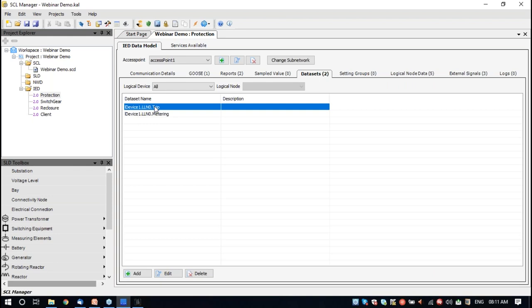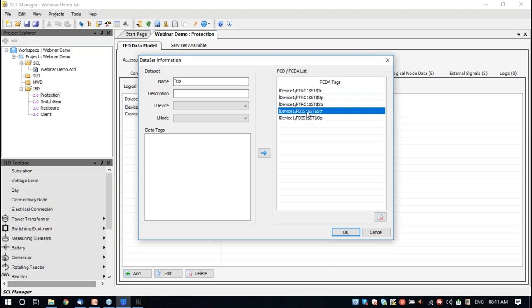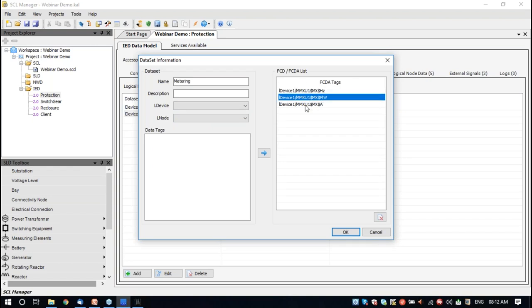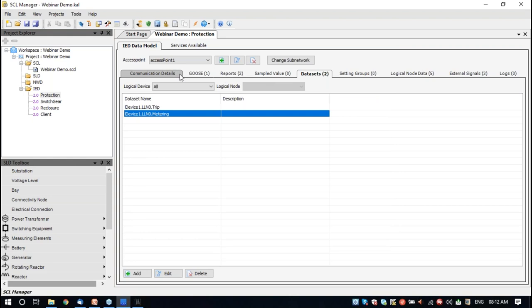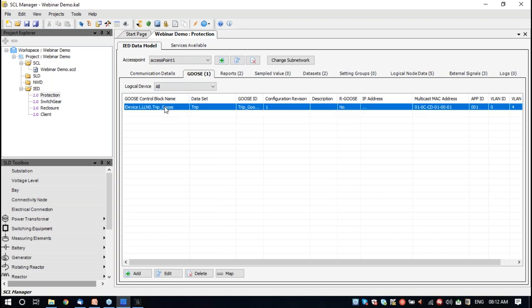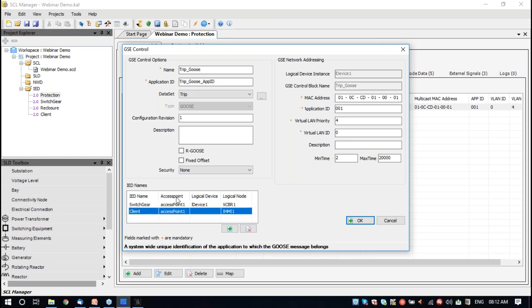There are datasets. The first dataset is a trip signal containing PTRC and PDIS, which is a distance protection function. In the second dataset, we have a few metering data points — frequency, phase voltage and current; we will focus more on frequency. We also have a GOOSE signal. The TRIP dataset will be sent out as a GOOSE packet, and you could see that this GOOSE is going to two remote devices — the TRIP GOOSE goes to the switchgear and also to the client. Using this mechanism, you will know which destination IEDs are receiving a specific GOOSE signal.